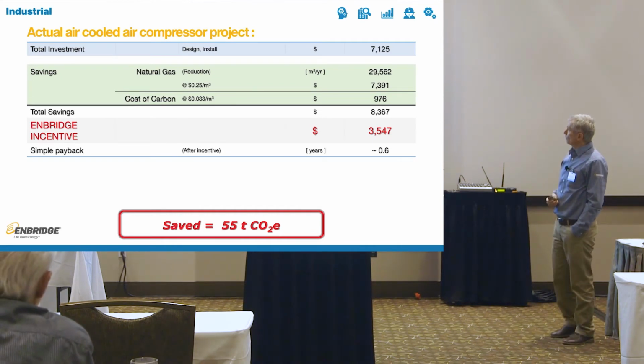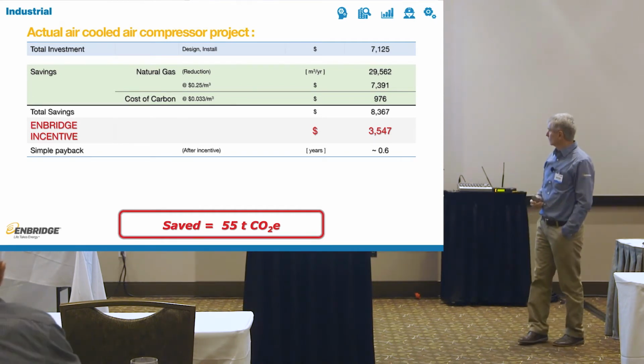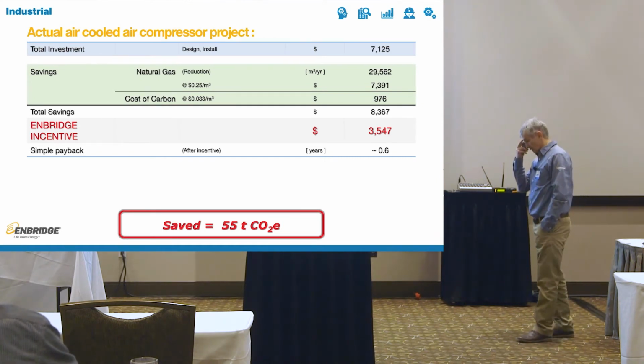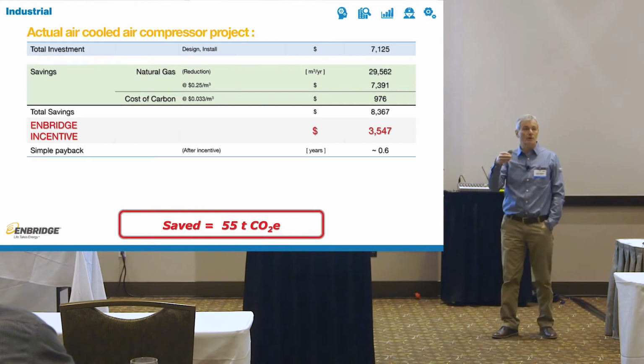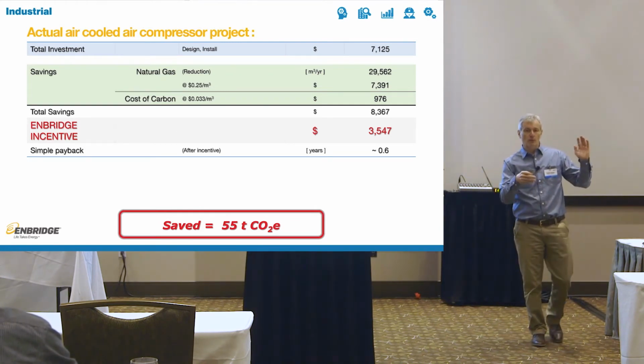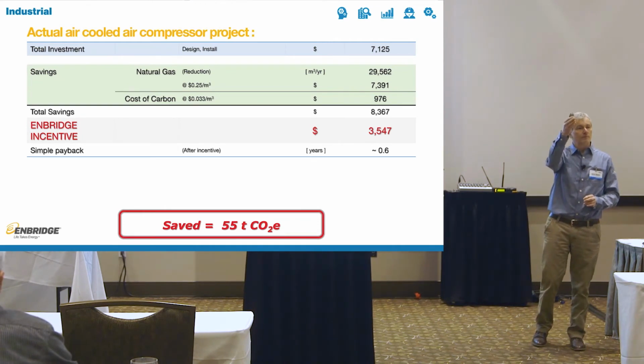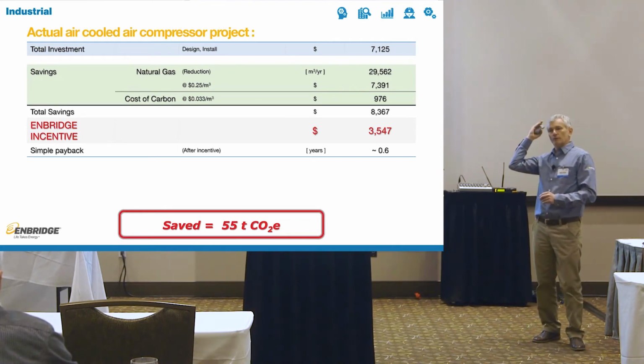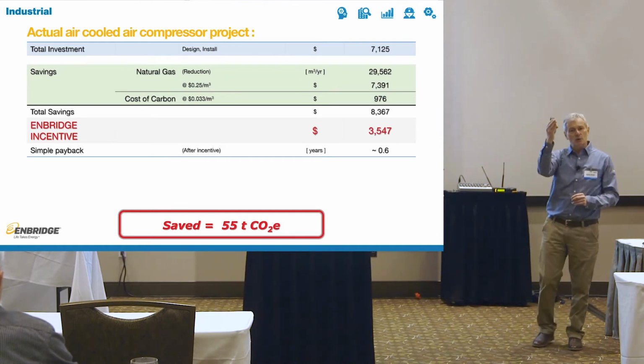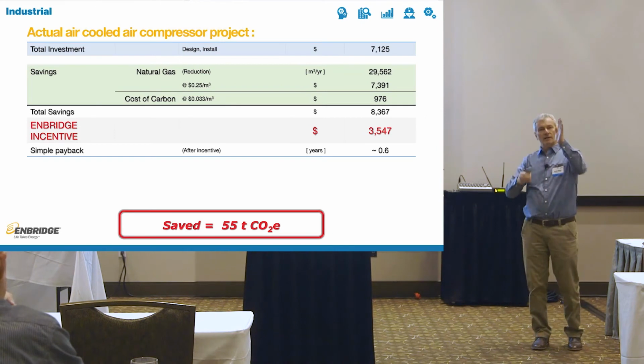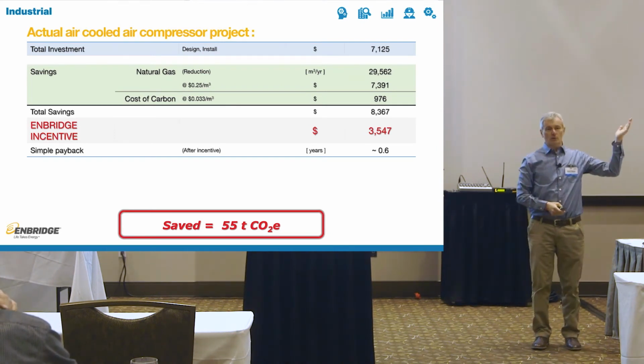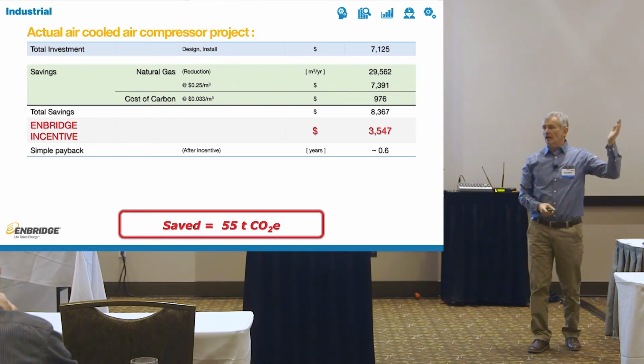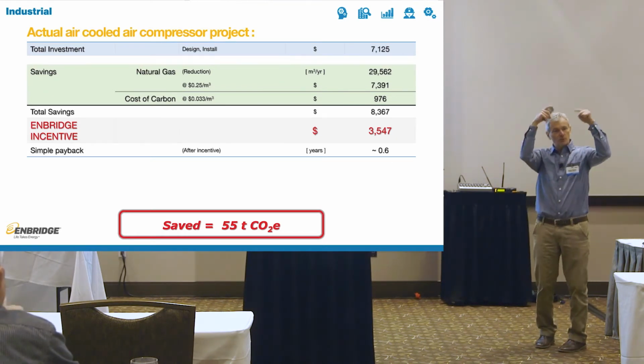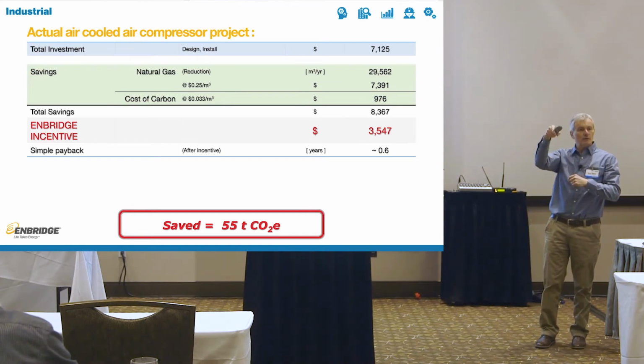This one is a little more complex. It's a water-cooled air compressor project. We came across that project because we were walking by the compressor, a 300 horsepower compressor, that was right next to the boiler room, with 2 pipes that went right above the compressor. One pipe was carrying warm cooling water into the cooling tower. The other one was bringing the city water into the boiler room. And we said, well, why don't we just put a heat exchanger between these two pipes? It reduces your cooling tower load and increases the makeup water temperature going in. Everybody's happy.